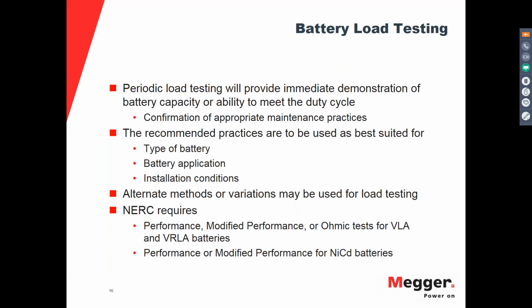These recommended practices are best suited for different types of batteries, battery applications, and installation conditions. And sometimes it's not possible to follow all of these guides and all of these recommendations. The test is, as I said, demanding, and sometimes you cannot comply with everything that is in the standard. So if you need to, you may use alternate methods, or you can introduce variations to the recommendations. However, there are two things to consider.